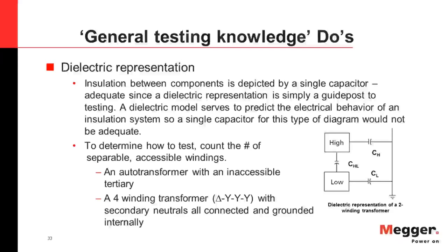On the other hand, you have a dielectric model that serves to predict the electrical behavior of an insulation system, so using a single capacitor for that type of diagram wouldn't be adequate. And as a helpful rule of thumb, in order to determine how to test, simply count the number of separable accessible windings. So I have two examples.